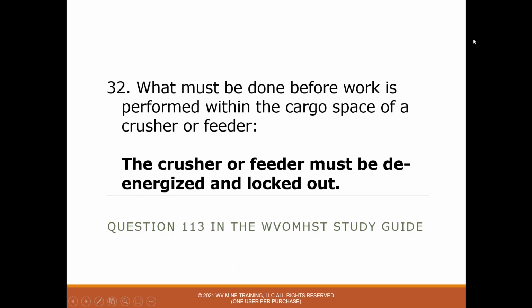32. What must be done before work is performed within the cargo space of a crusher or feeder? And the answer is the crusher or feeder must be de-energized and locked out. So we always talk about electrical equipment being locked and tagged out, and that's absolutely true. We lock and tag out every piece of electrical equipment if we're going to be working on the circuit.